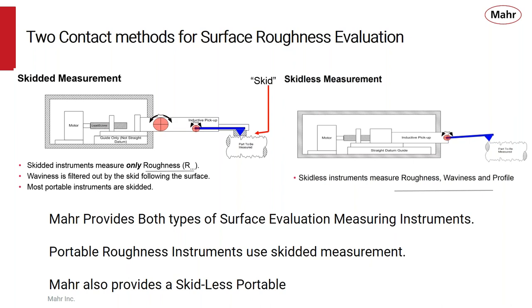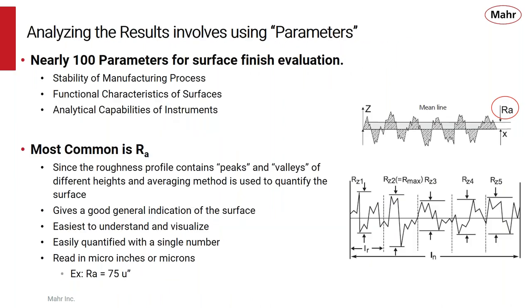Most portable roughness instruments are skid measurements, but Mahr also has a skidless portable system. There are lots of different parameters to allow us to evaluate surface finish — in fact, over 100 of them. Those different parameters have different functions specifically to evaluate how the surface is to perform. You can have parameters meant to evaluate the manufacturing process, the characteristics of the surfaces, or for specific applications such as oil retention.